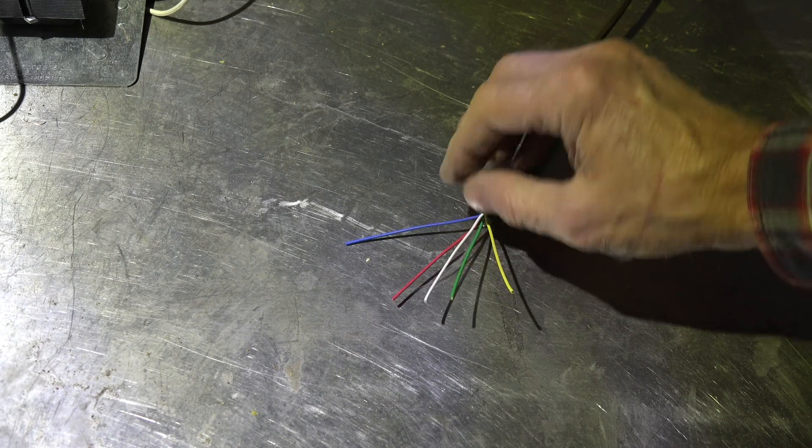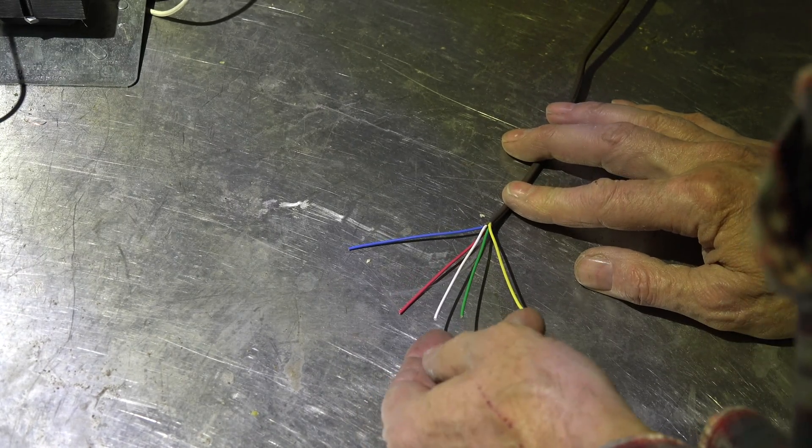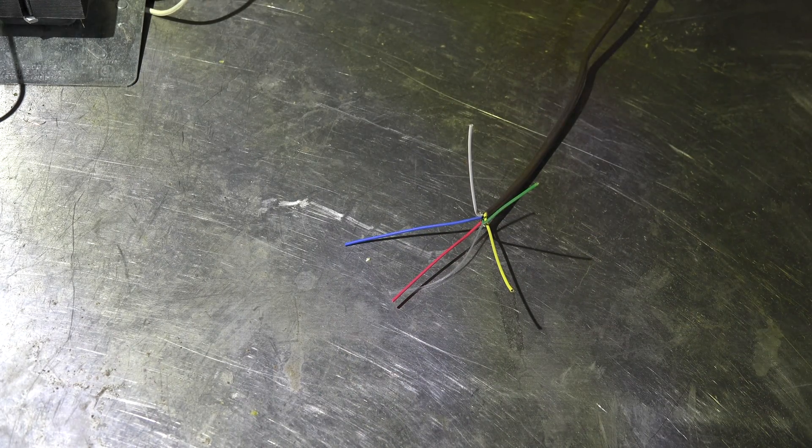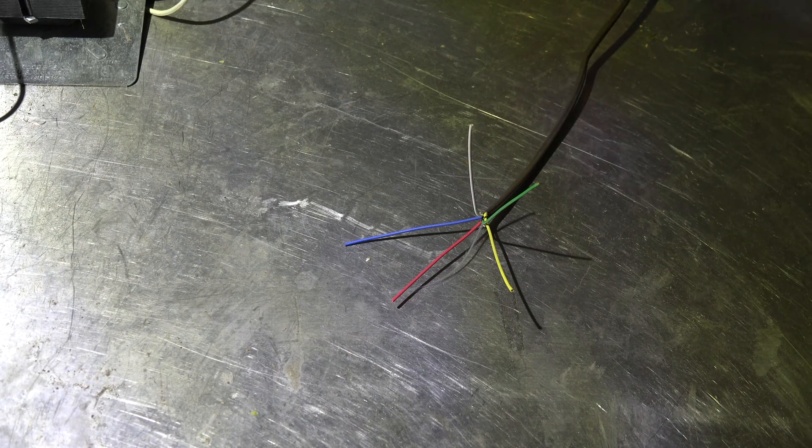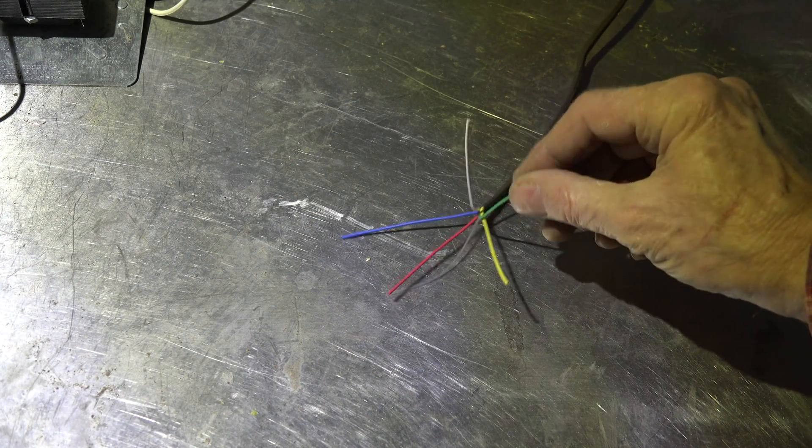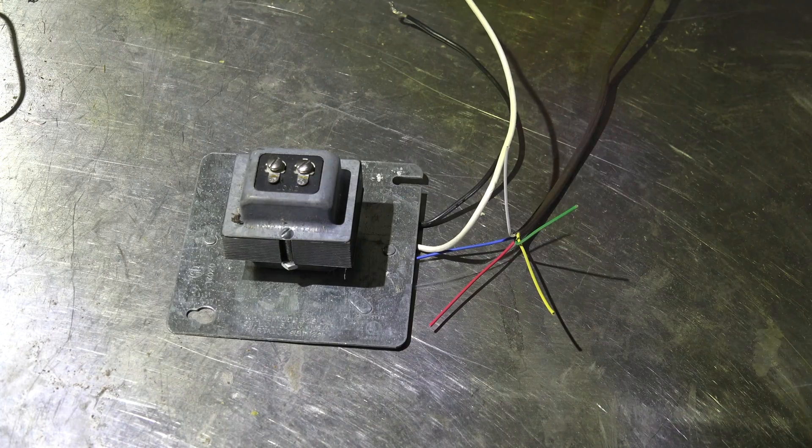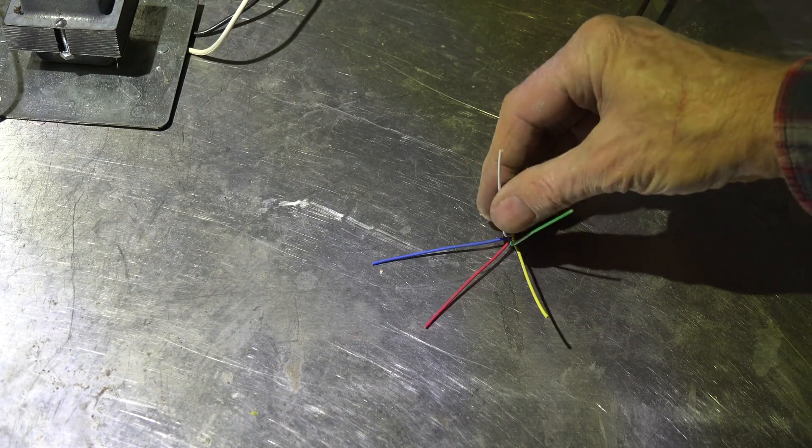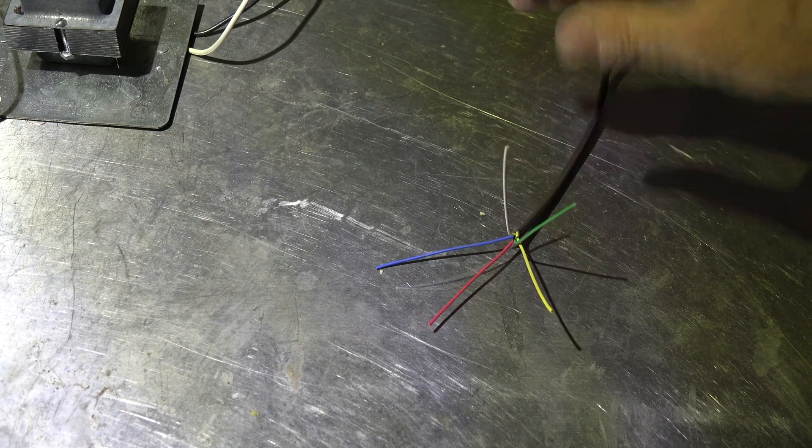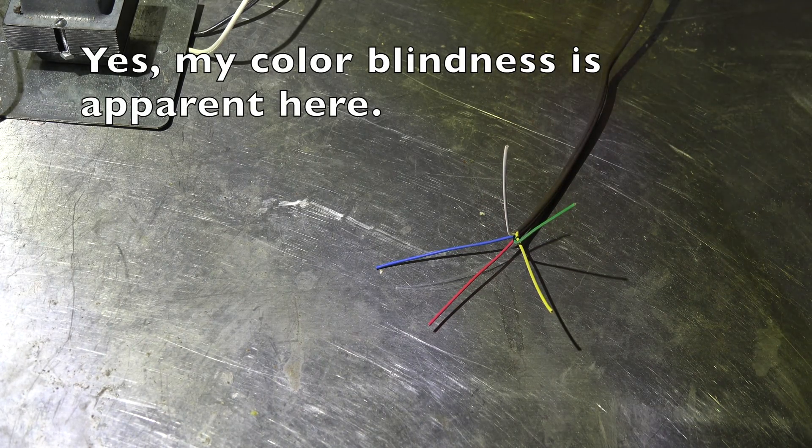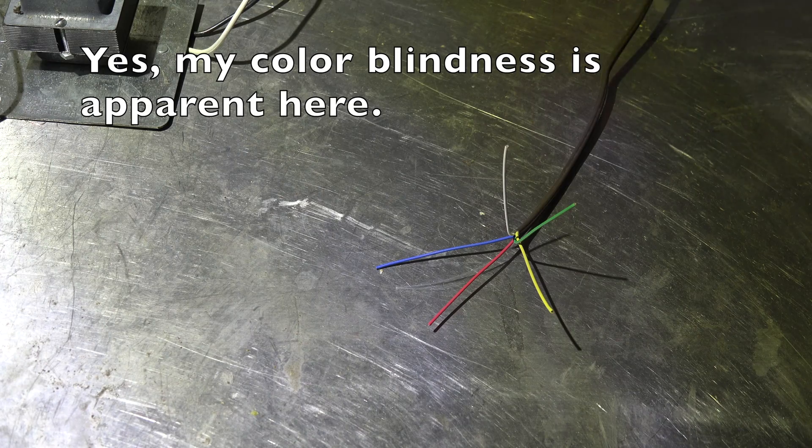Your older thermostat may have only required two wires, in which case you probably would have these two, the red and the white, hooked up. The red comes from the transformer, and the white comes back down to control the furnace.